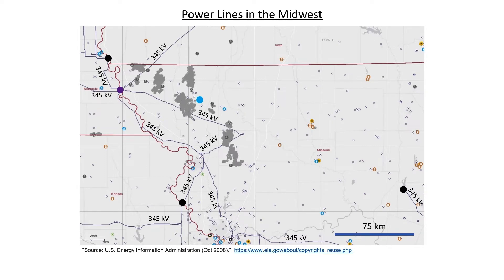Let's now take a look at the high voltage transmission lines here in the region. In this region, the highest voltage is 345 kilovolts. These 345 kilovolt lines mainly run to and from the big power plants that I highlighted earlier. The turbines inside the power plants, though, don't generate electricity at 345 kilovolts. Typically, turbines will operate in the neighborhood of 10 to 20 kilovolts. So all these power plants have step-up transformers just next to the power plant in order to get the high voltages needed for transmission.